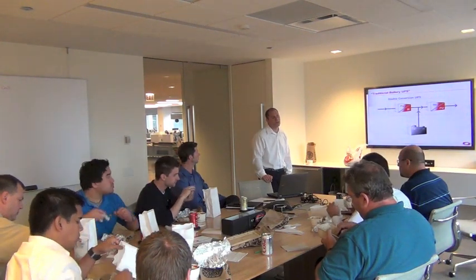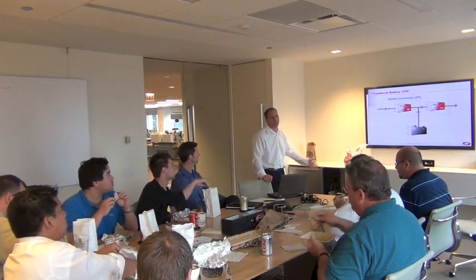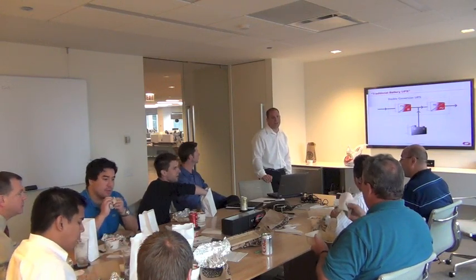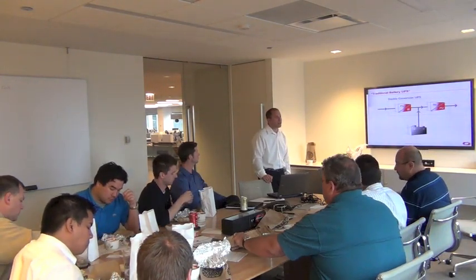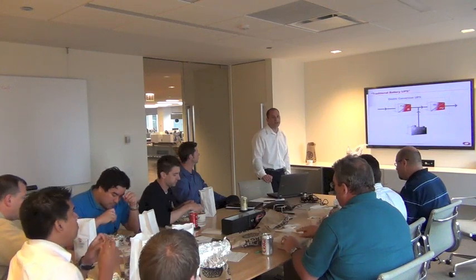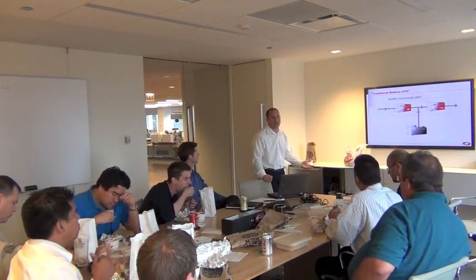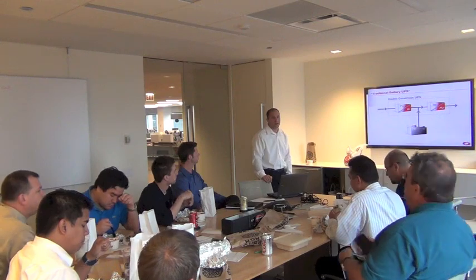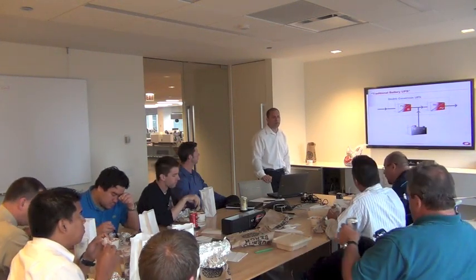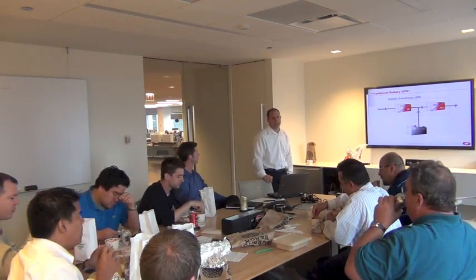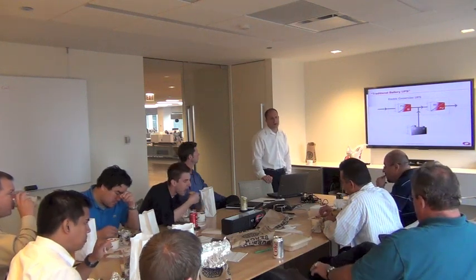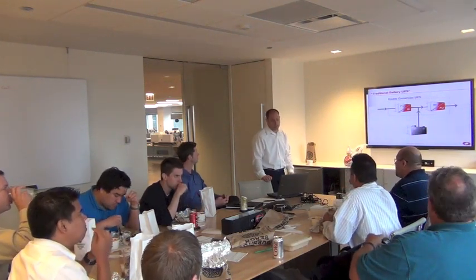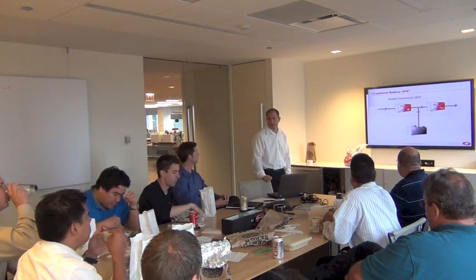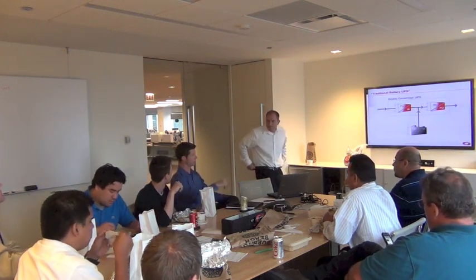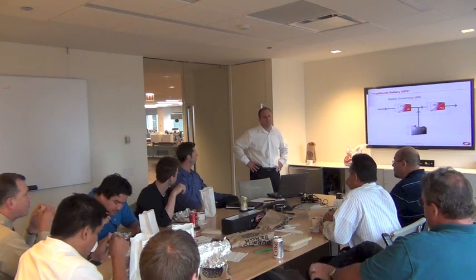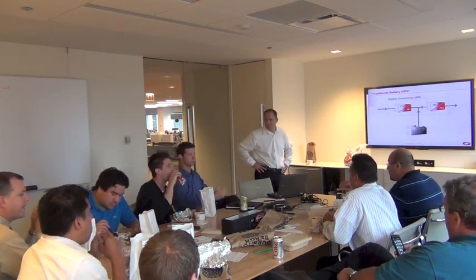But the UPSs in general are getting more efficient. Your traditional double conversion UPSs used to be like 91% was considered good. Actually, there was a study done and it showed about 12% of losses in data centers were in the UPS. So most of them were operating at pretty low efficiency levels 5, 6 years ago. But they are getting more efficient. Probably 93 to 94% efficient is not unlikely to see at 100% load. I think Liebert publishes 93.6% efficiency and Power publishes 94% efficiency, or 99% in eco mode, which is basically taking that double conversion process out of it.